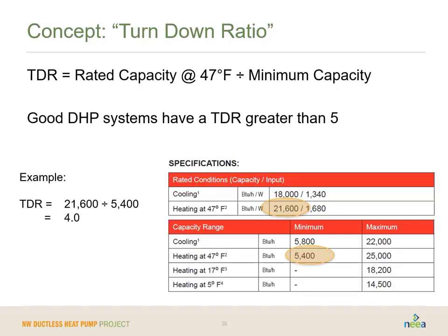So here we've got a system, its standard rated capacity is 21,000 BTU, almost 22, and its minimum capacity is 5,400. So this has a turn down ratio of 4. So that's not bad. If it was 6, that would be tremendous, but anything 3 or above is going to be pretty decent. The really good systems have turn down ratios greater than 5. Decent systems have turn down ratios greater than 3.